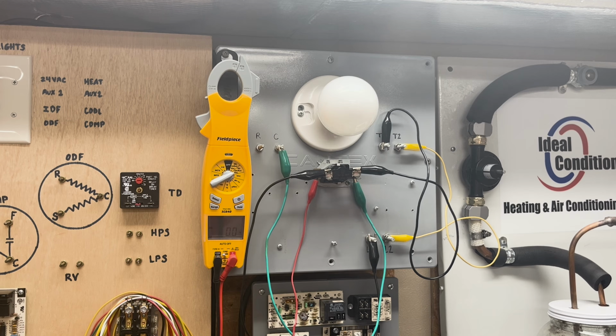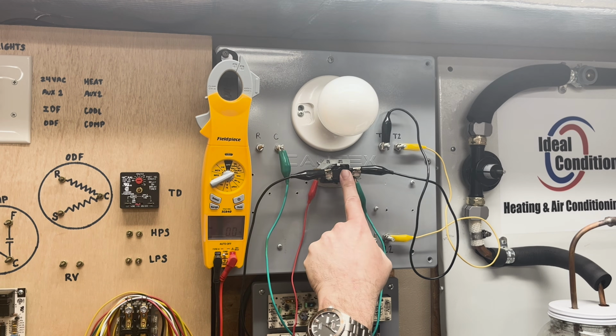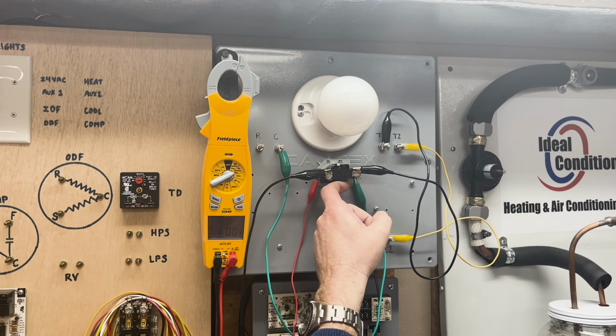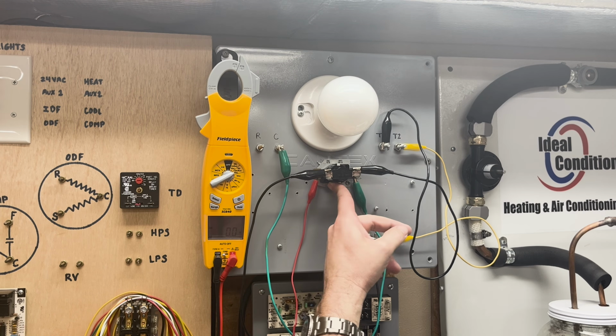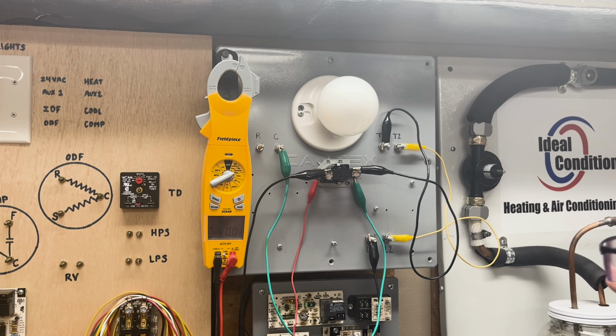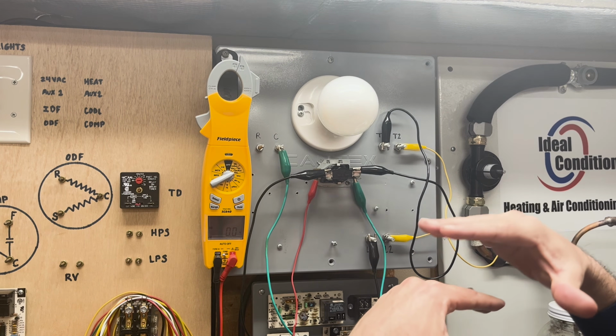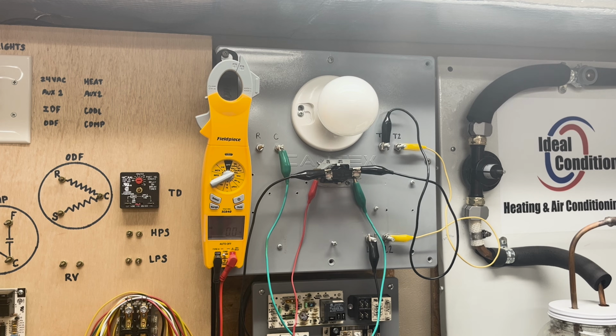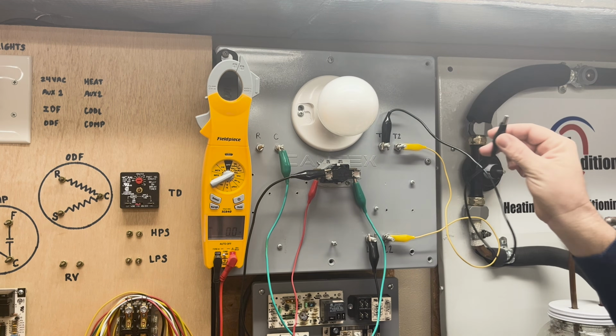45 seconds. So, like I said, if you had one that was taking you more than a minute, replace it. I can almost feel the warmth on this relay. It's not hot, but I can almost feel the warmth on it. So that could also be it's taking longer for that area to cool down. There's a lot of heat trapped in there. And so maybe if it's off for a while, maybe its off time is really 30 seconds. But I can still get a lot of efficiency out of this thing. This is a really good relay. I'm going to go ahead and show you how I can tell if I have...